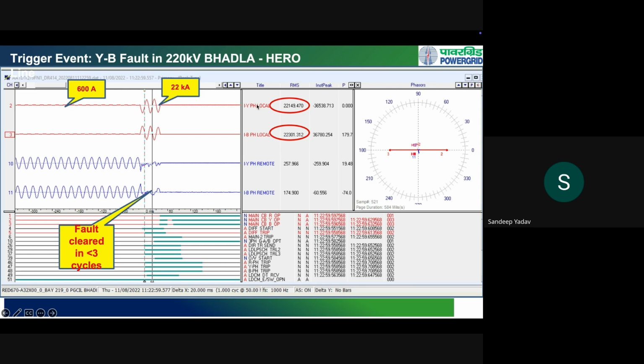And if you take a look at their phase angle, if you take the Y phase as reference, it becomes 0 degrees. And the B phase is 179.7, which is equal to 180 degrees. Also, if you look at these two phasors, phasor 2 and phasor 3, which are nothing but the Y phase and B phase currents, they are totally in phase opposition, which is expected from a synchronous source. So Y and B are both in phase opposition and both have almost the same 22 kiloampere fault current. And this is the fault contribution from the grid side.